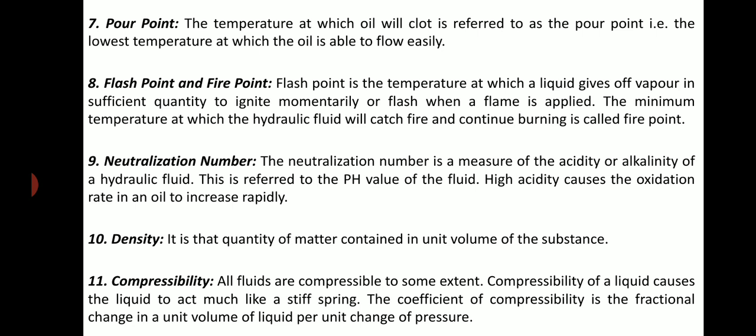Flash point and fire point: Flash point is the temperature at which a liquid gives off vapor in sufficient quantity to ignite momentarily or flash when a flame is applied. The minimum temperature at which the hydraulic fluid will catch fire and continue burning is called the fire point.